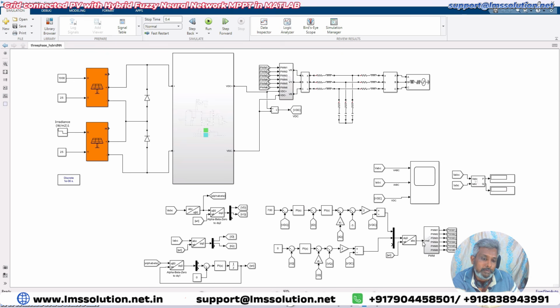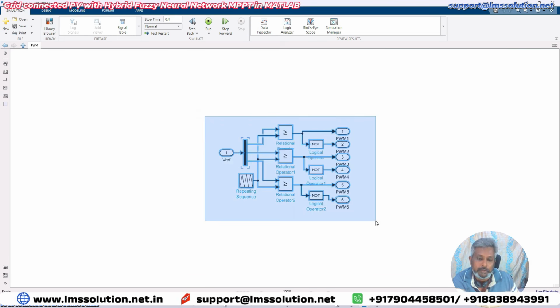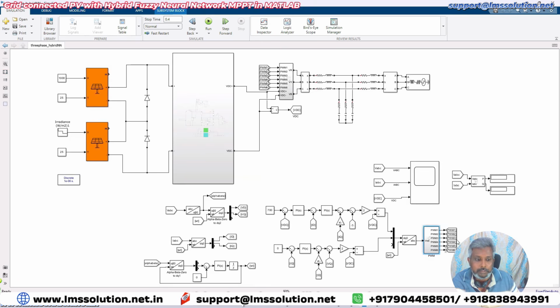After that we are converting that control signal into ABC form by using inverse park transformation. After converting that control signal into ABC form, there are 3 signals that come from that control signal. They are going to be compared with the triangular wave. That is known as the sinusoidal pulse width modulation technique. You just take the sinusoidal control signal, compare with the triangular wave, and then we are getting the 6 pulses. These 6 pulses will be used to control that inverter. This will control the inverter, and it is going to maintain the DC link around 700 V, and then whatever power we are generating from PV will be sent to the grid point.